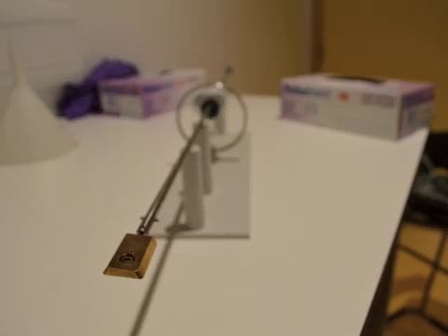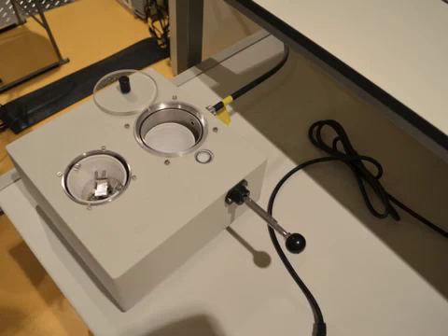The next step is that this holder gets placed on a long rod, which is basically the rod that takes it into the SEM system. And then you have to freeze it. What we do is fill up these compartments with slush nitrogen, which basically is liquid nitrogen that we then cool further down. So you get a mixture between liquid and solid, and the temperature of that is even slightly lower. And you dunk your sample in there, so you freeze it very fast.